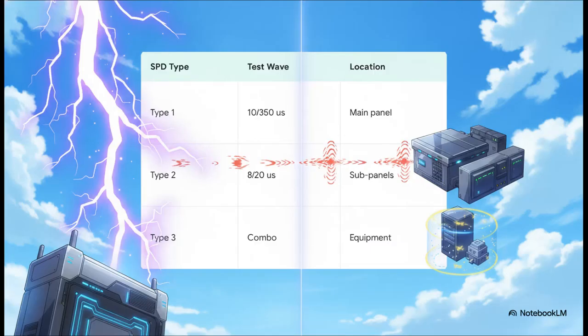Think of this table as your ultimate SPD cheat sheet. A Type 1 SPD is heavily tested against a massive 10/350 microsecond full lightning wave. You slap this guy at your main incoming LV panel. A Type 2 SPD handles the shorter 8/20 microsecond induced surges, which is absolutely perfect for the inverter AC output or combiner boxes. And finally, a Type 3 SPD is your last line of defense, sitting right at the equipment terminals. Pro tip, never, ever reverse this order in your designs.